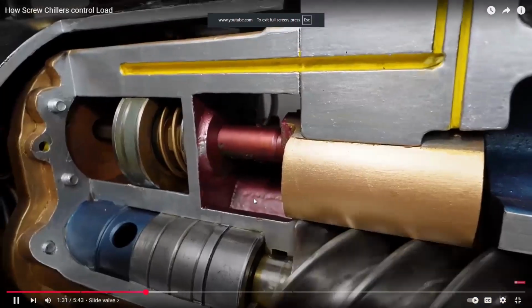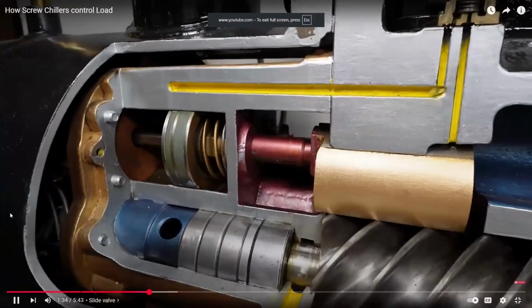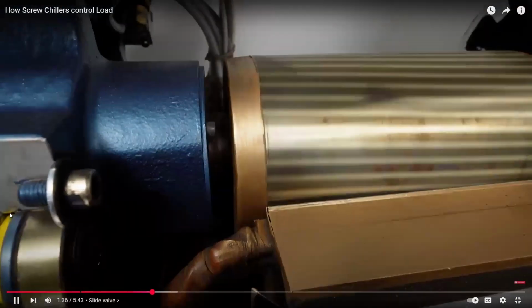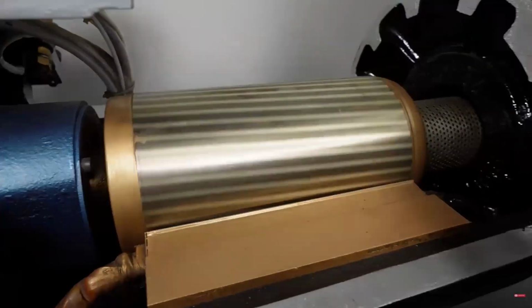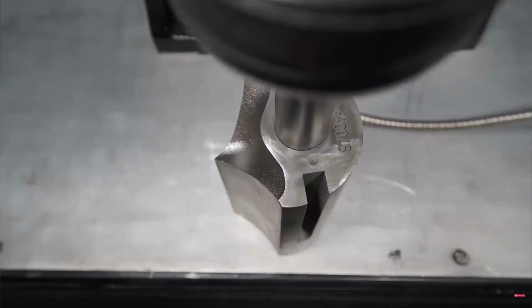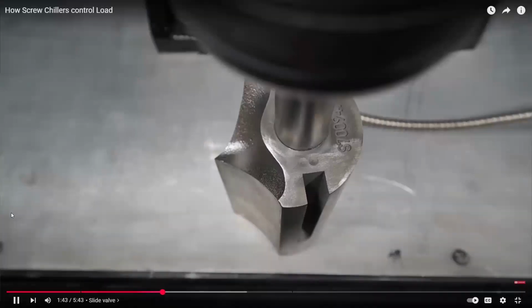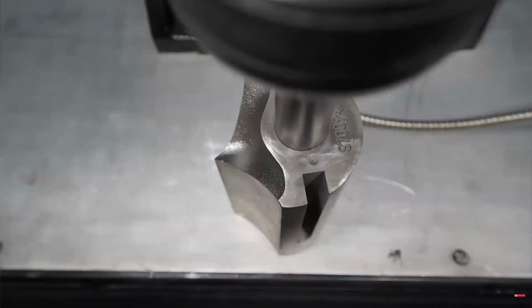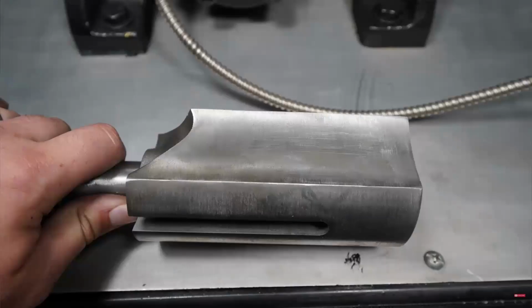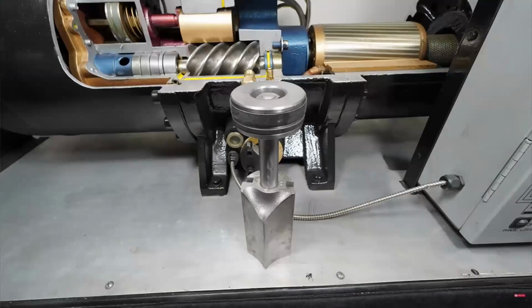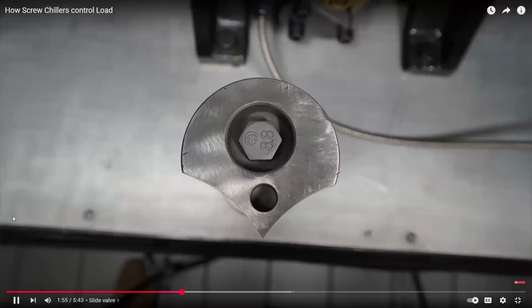The valve moves to a fully unloaded position. There's still direct compression happening, but it's just a very minimal amount—it may only be 10-20% of what that compressor's actual volume is capable of moving through it. As that slide moves and increases or decreases capacity, it's also increasing or decreasing our current load through the compressor. That's one of the main methods used to control how much we stage up or down.